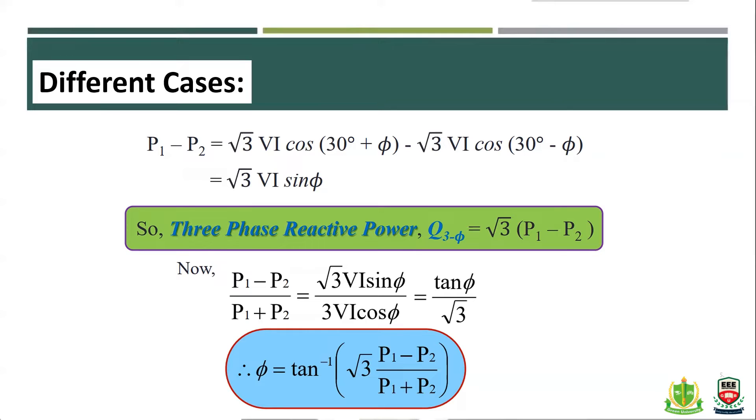The equation for the two-wattmeter method is P1 minus P2. Going to the bottom of the equation, P1 minus P2 gives root 3 times V times I times sine(phi). The total equation gives root 3 times VI times sine(phi) for three-phase power. Also, tan(phi) equals root 3 times (P1 minus P2) divided by (P1 plus P2).